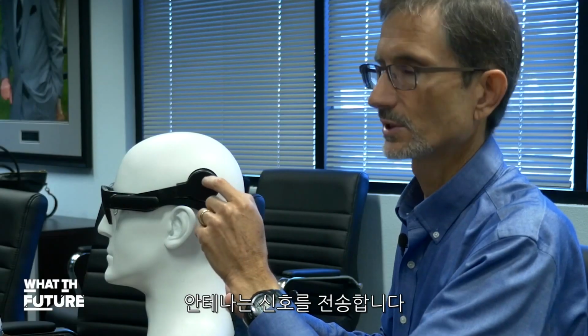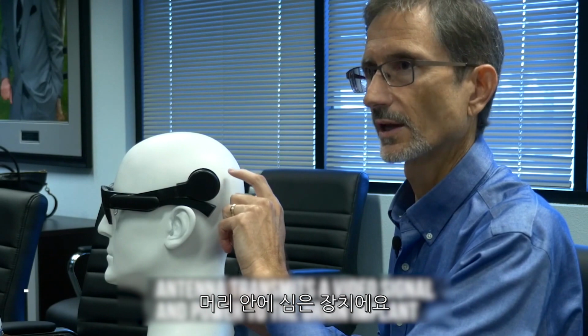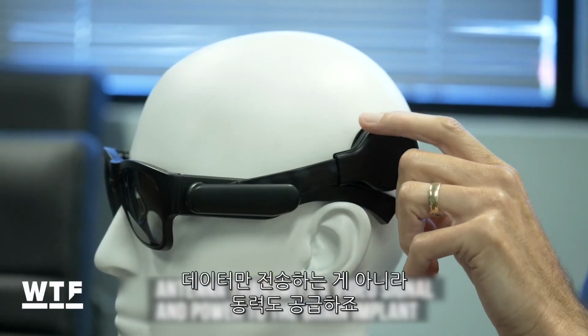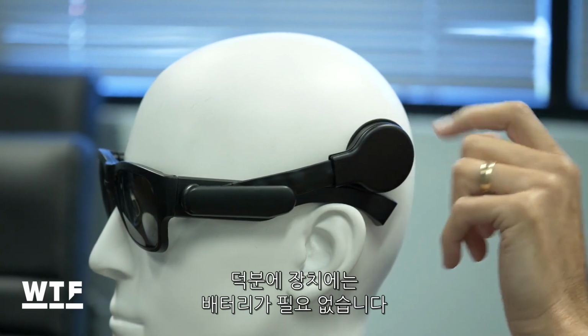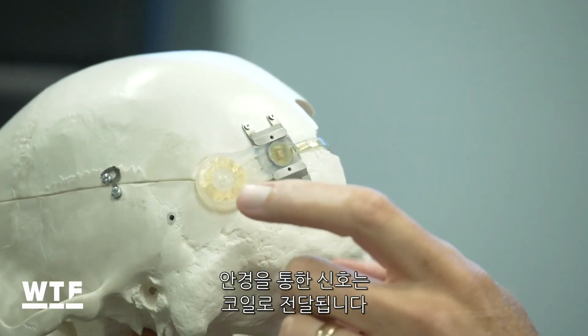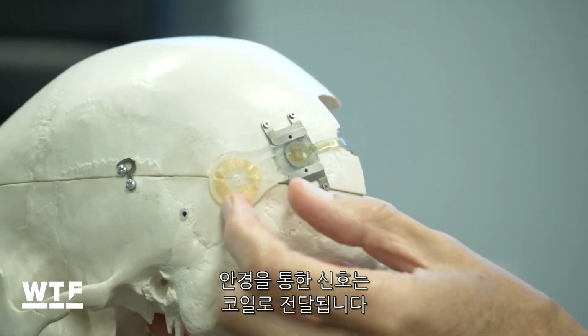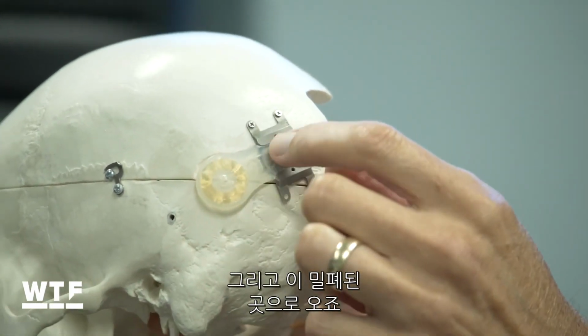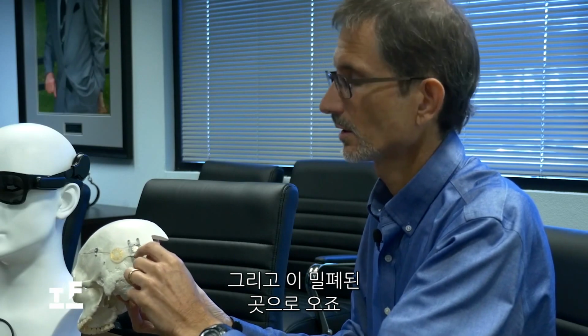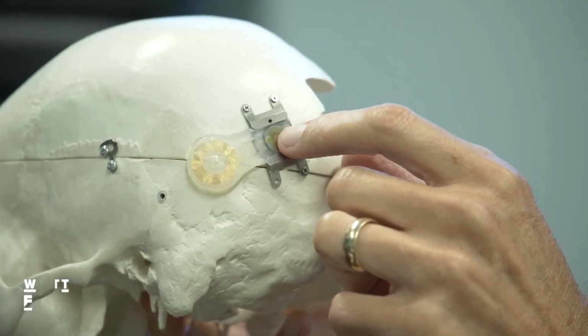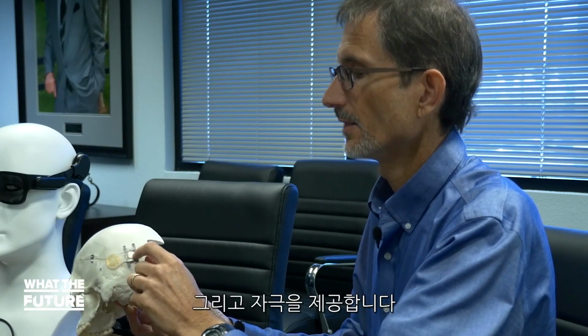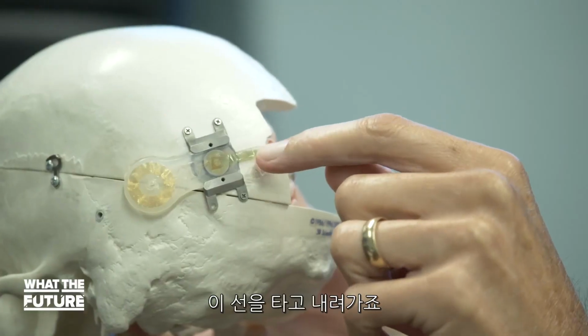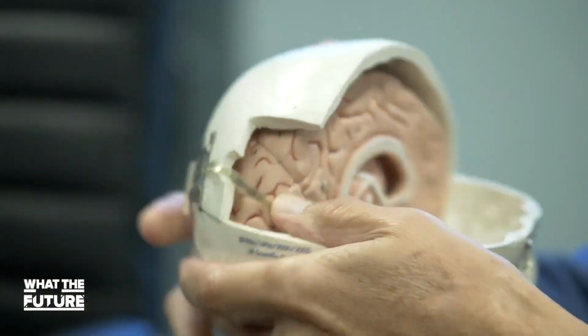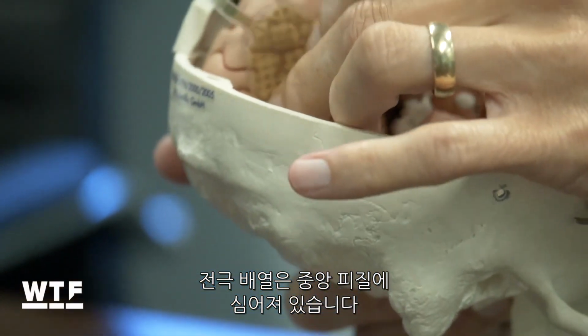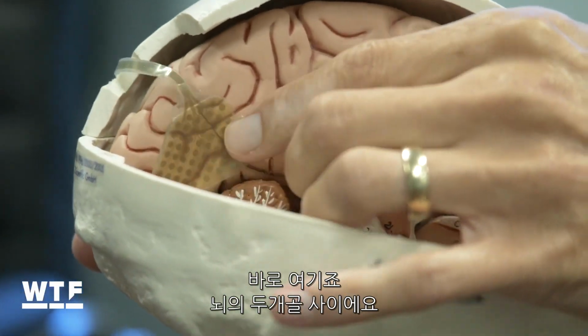So this antenna transmits the signal to the implant inside the head. Not only does it transmit data, but it also transmits power. So the implant doesn't need to have a battery. So the signal from the glasses is received by this coil here, this antenna, and then it goes to the hermetic package here. This is where the electronics are that decode that signal and then provide the stimulation pulses that go down this cable to the electrode array. The electrode array is implanted on the visual cortex right there between the 2 halves of the brain.